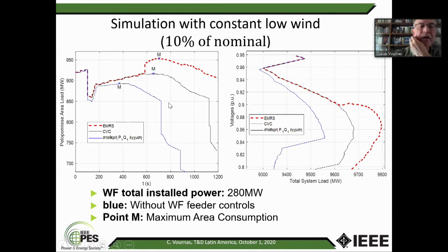If you go with the black line, which is constant voltage control and capacitor support, you have an increase of 20-something megawatts. You can go close to the initial value, but not quite. And with the emergency reactive support from the wind farms, you have a gain of about 60 megawatts in maximum power transmission, which means that the system can withstand the initial consumption. So at this point, they have to stop. There's no need to go any further because the increase of demand is only needed if the load is not served.